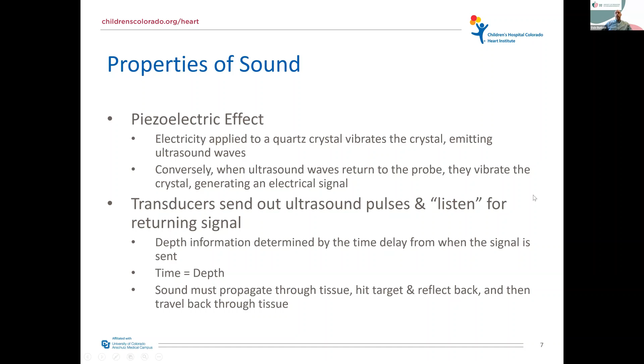It's also important to note that higher frequency signals provide better resolution. So if you're going to be imaging a little baby, you're going to want to grab the 12 probe to get the best images possible and not use the adult probe. And conversely, if you're using the 5 megahertz probe or 4 megahertz probe, you're going to want to use that for the adults because the tissues are further away. So higher frequency gives you better imaging resolution because you're having more signals hit the structure and bounce back. So you actually get a little bit more detail with that.